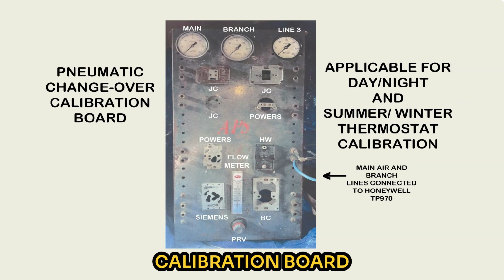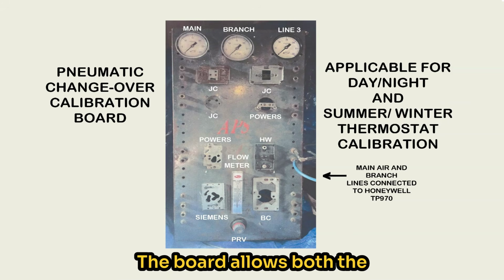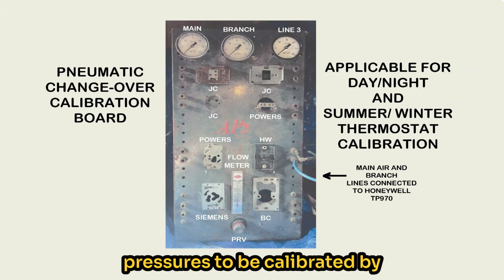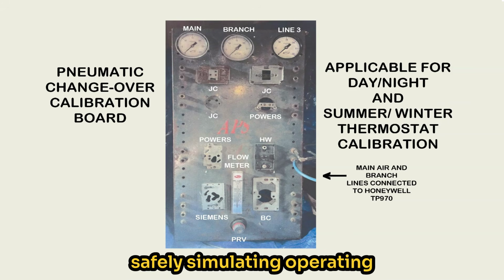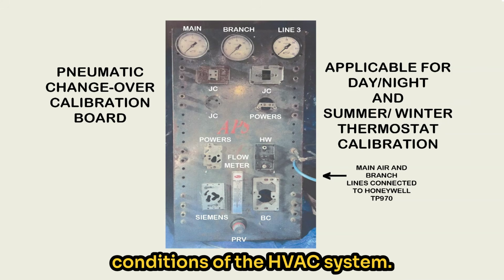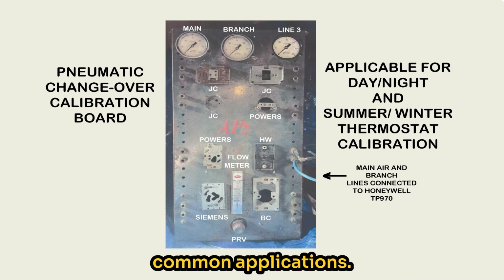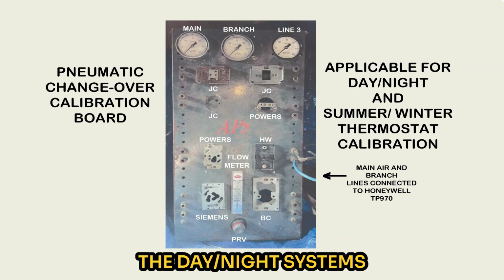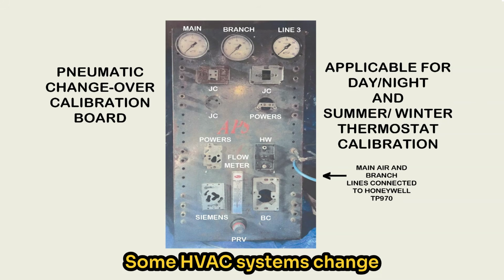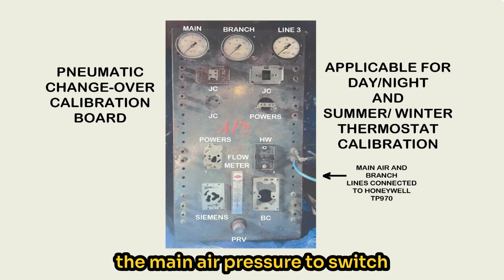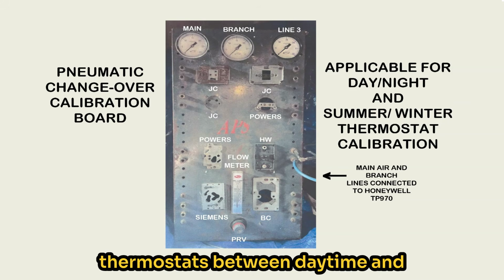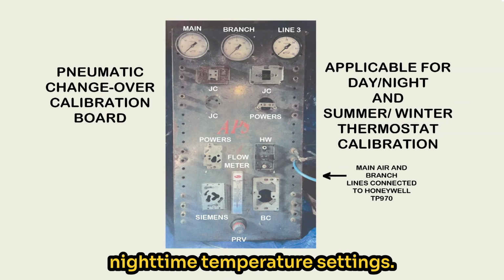The purpose of the calibration board. The board allows both the temperature set points and the mode changeover set pressures to be calibrated by safely simulating operating conditions of the HVAC system. There are two common applications. The day-night systems. Some HVAC systems change the main air pressure to switch thermostats between daytime and nighttime temperature settings.